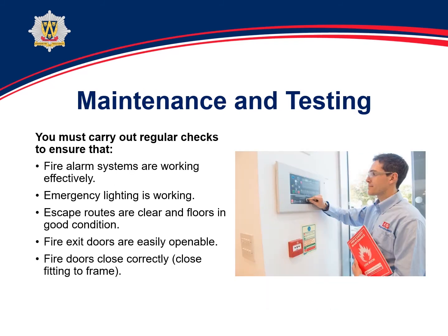So all of these systems that you've put in place now need to be properly maintained. So your fire alarms need to be tested, emergency lightings are in working order, the escape routes are clear. Those final exit doors are openable during winter months because they are external doors. They can swell and become difficult to open. So it's important to keep checking them on a regular basis.